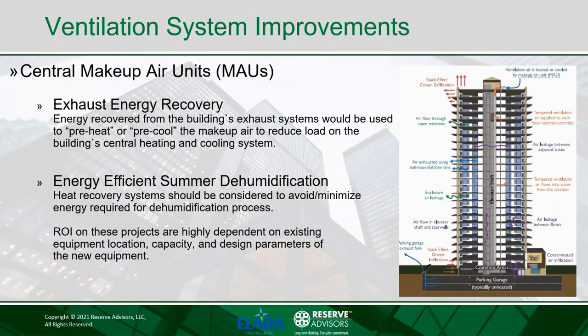When it comes to building central ventilation systems, there are several projects that should be considered not only to increase energy efficiency, but also to improve building pressurization, comfort, and some issues resulting from stack effect because we have a high-rise building. One of the potential projects I'd like to talk about is exhaust heat recovery. With an exhaust heat recovery system, energy recovered from the building's exhaust systems would be used to preheat or pre-cool the makeup air to reduce load on the building's central heating and cooling system. Energy savings and return on investment on these types of projects are highly dependent on existing equipment location, capacity, and design parameters.